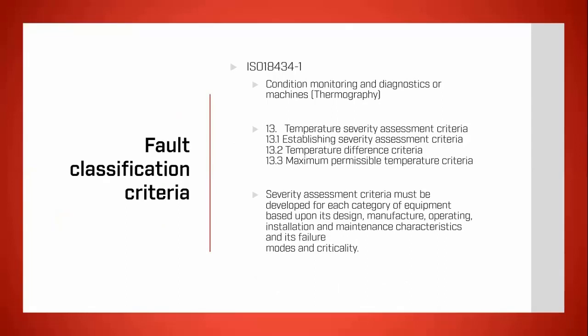For classification criteria within thermography, we have a really useful standard: ISO 18434-1, 'Condition Monitoring and Diagnostics of Machines — Thermography.' Chapter 13 contains a whole section on severity assessment criteria. It can be established on individual machines or components and is based on many factors including safety of personnel, temperature rise versus historical data establishing rate of deterioration, and time to failure. Applications include temperature rises of critical machines, mechanical components, bearing temperatures, and electrical connection rises.